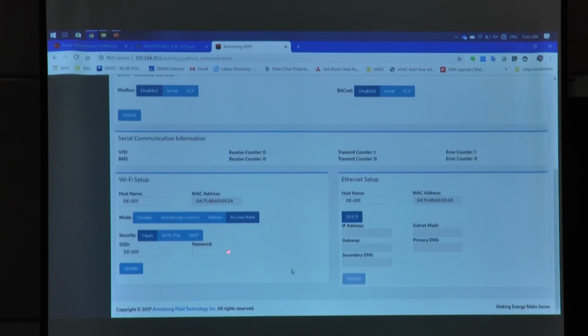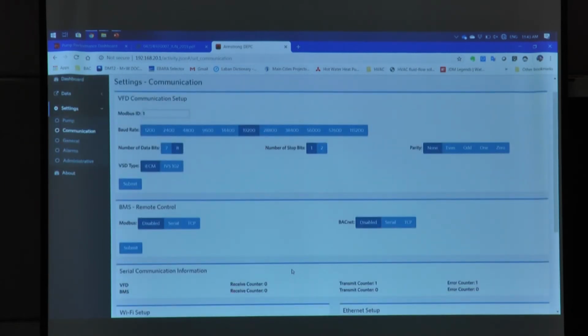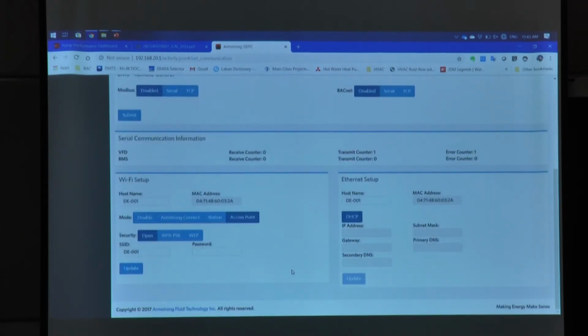And below shows it has two connections. It has the Wi-Fi setup and also the Ethernet setup. If you would like to use the Wi-Fi setup, such as this pump shows, we have different modes, such as disable, Armstrong Connect, station, and access point. Now the current mode is the access point. In this mode, it can act as a router, so we can use our cell phone or desktop to connect to the pumps. If you use the station mode, it only acts as a substation. And for the Ethernet setup, you can set up the IP address, the host name, and so on.